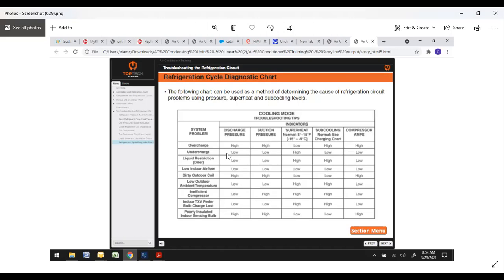Liquid dryer restriction. Now, this can be funny, because if you have a restricted dryer, you can actually end up with high discharge pressure if it's sitting right outside the unit. So conceivably, you could have high. They're saying low suction pressure would be low because your refrigerant is actually flashing, so it's being metered at the filter dryer. So that is the first metering device. At that point, it's hitting your TXV or your piston. You'll also have very high superheat because it's not going to cool. You'll also have high subcooling because it's not metering properly. And since it's not working super hard, you're going to have low amperage.